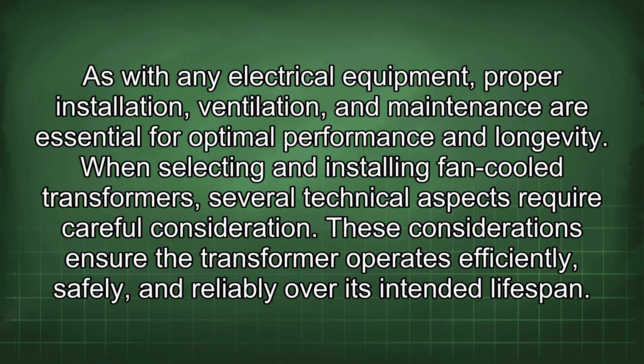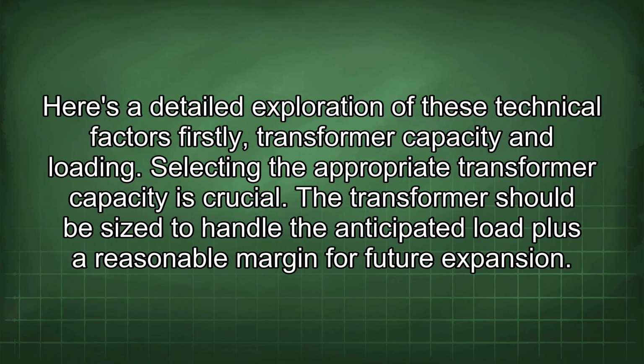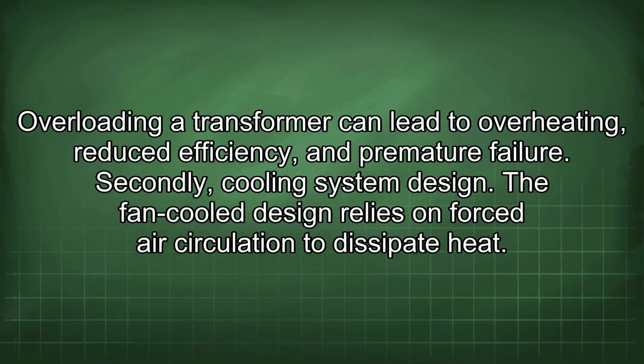When selecting and installing fan-cooled transformers, several technical aspects require careful consideration. These considerations ensure the transformer operates efficiently, safely, and reliably over its intended lifespan. Here's a detailed exploration of these technical factors. Firstly, transformer capacity and loading. Selecting the appropriate transformer capacity is crucial. The transformer should be sized to handle the anticipated load plus a reasonable margin for future expansion. Overloading a transformer can lead to overheating, reduced efficiency, and premature failure.